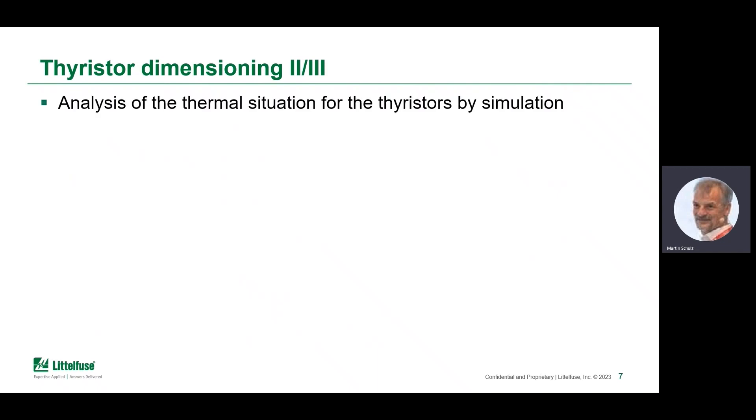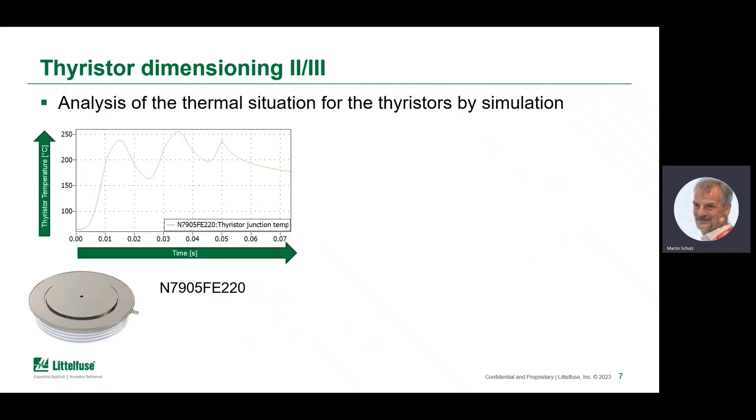Dimensioning the thyristor — because there's not a single thyristor that can do the trick — demands analysis of the thermal situation. Handling short-circuits is more pulse power than continuous power, and the only thing of interest is the chip temperature. Taking a large-scale thyristor, it can easily be seen that even this high current only leads to 250°C for the junction of the chip.